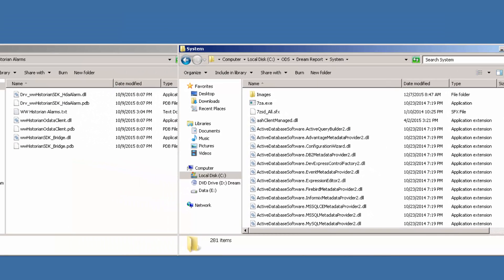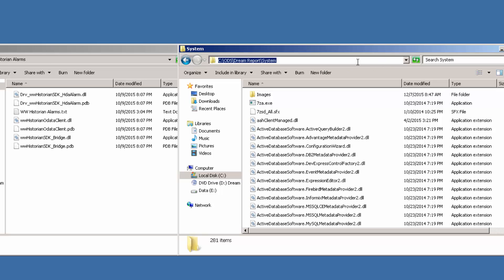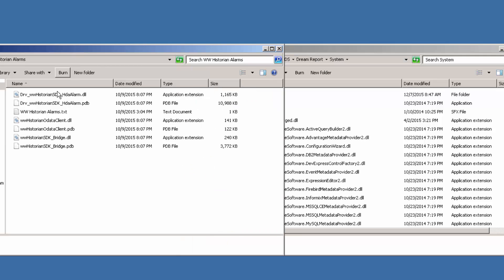Now we need to apply the hotfix per the instructions listed in the download file. So the hotfix includes three DLLs and the corresponding PDB files. To apply the hotfix, we're going to need to stop any running DreamReport project, close the DreamReport studio, and place the files in the directory shown here, which unless you altered it from the default, it's c colon backslash ODS DreamReport system.